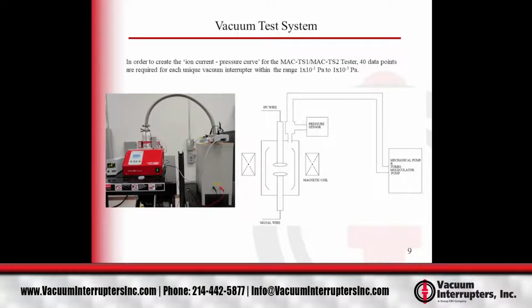The way that we're able to produce these current versus pressure curves is by connecting a vacuum interrupter that has a vacuum fitting welded to it. We connect that vacuum interrupter to a high vacuum system capable of pumping it down to new vacuum interrupter levels. We also have a pressure transducer that's measuring the pressure while we're pumping it, and some insulating links between the vacuum interrupter and the pump, which allow us to apply the high voltage at the same time. So we pump the vacuum interrupter down to a new vacuum interrupter pressure, perform the MAC test on it, measure the current, and then vary the pressure all the way to the point where it fails the test. This is the way that we're able to produce those curves for the MAC test set.